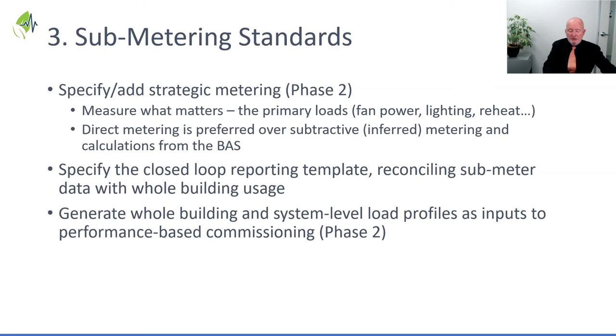Sub-metering standards - I think both St. Catharines and, not sure about Women's College, but the strategic metering has become apparent as really valuable through this project, something you will need to add. So those conversations will continue, and direct metering is always preferred over inferred or subtractive metering. In other words, if I'm using this much energy here and that much there, then the difference must be what this one is doing - those tend to be unreliable and the source of considerable disputes. And once again, these sub-metering profiles becoming part of the commissioning process, so you can validate every one of the profiles that matters.